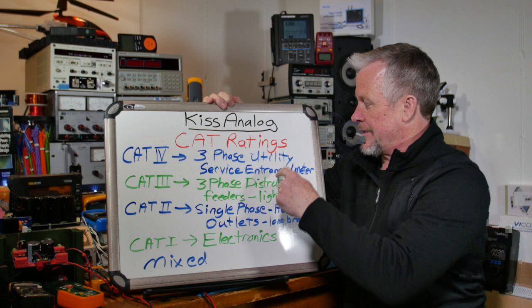So you have the potential fault current. That's one of the things you've got to be careful about. Then the voltage level and the transient level. Those three things are what a meter is designed to protect against, basically. You have the voltage isolation for both the voltage and the transients, and the proper fuse in there for the fault current. Now, one more category.